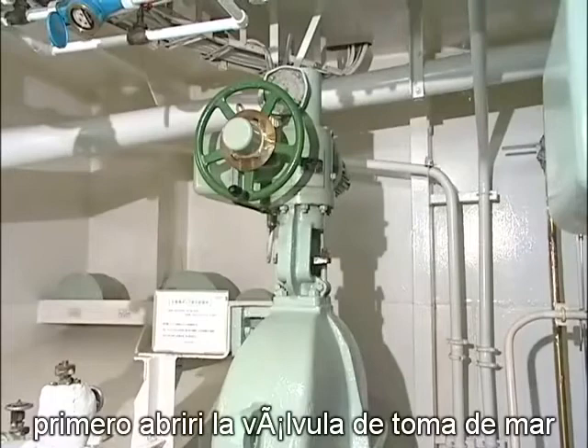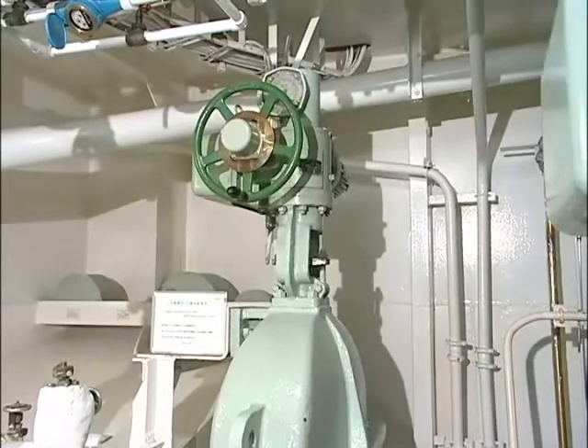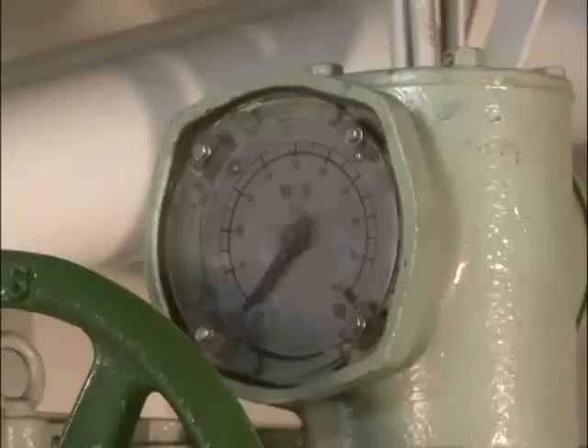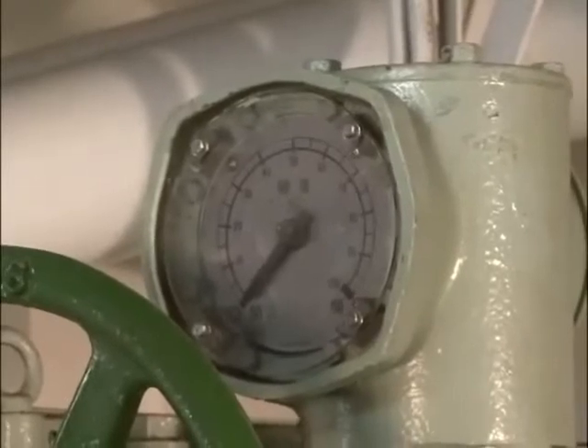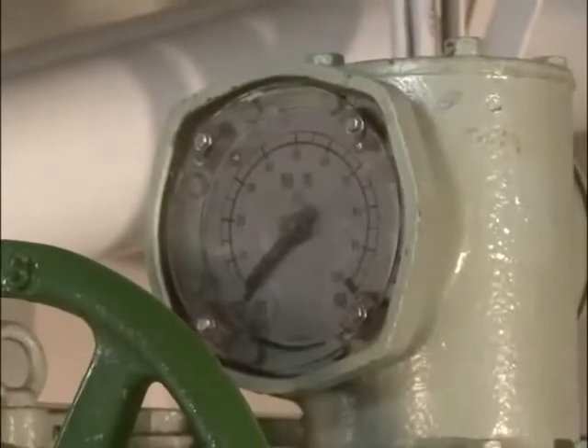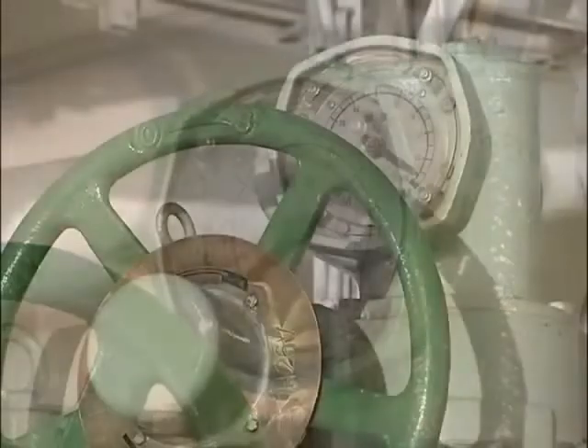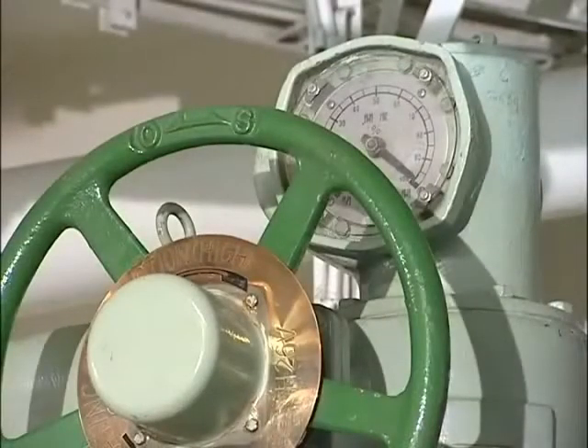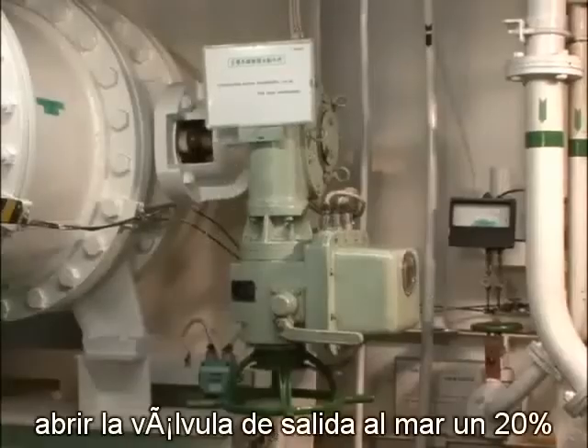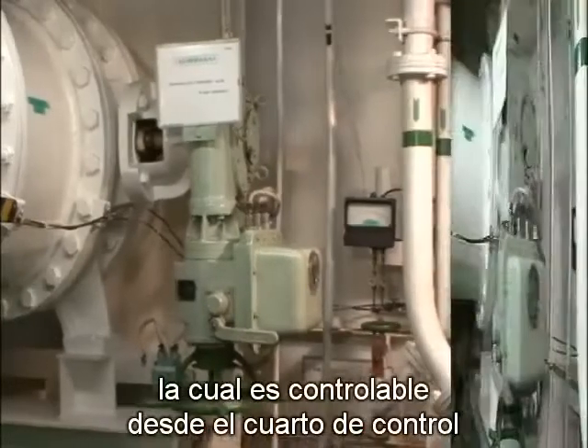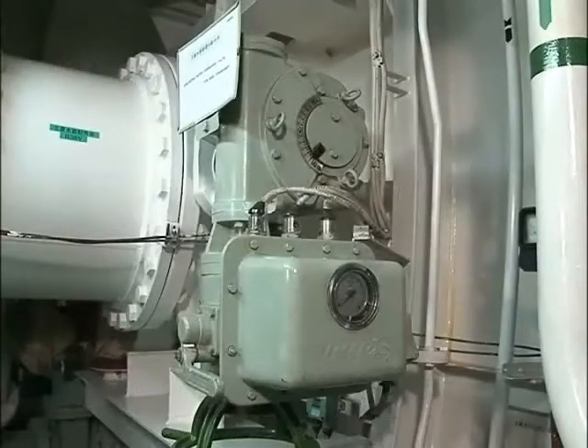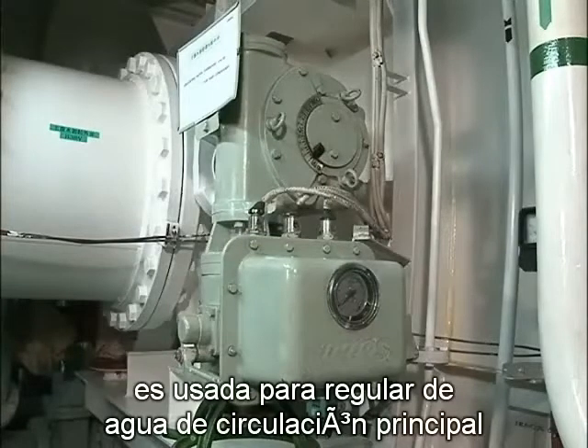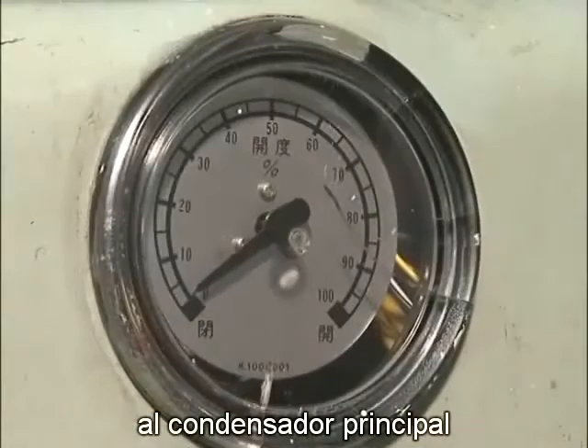First, open the sea suction valve. Next, open the overboard valve to 20%. The overboard valve, which is controllable from the control room, is used to regulate the flow of main circulating water to the main condenser.